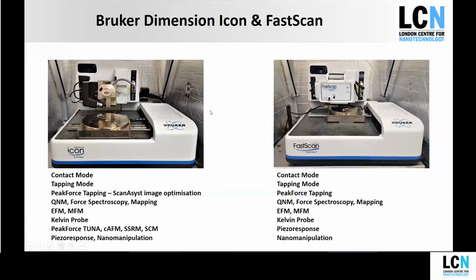So this is our Dimension series of instruments. This is a Dimension Icon over here. It's a tip scanning AFM, with a max scan size of 93 microns in X and Y and 13.5 in Z. We can do standard contact mode and tapping mode. You can do this on all our instruments. This one also has peak force tapping, which is a newish AC mode imaging technique.